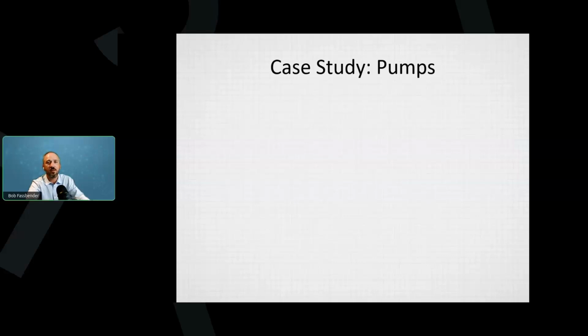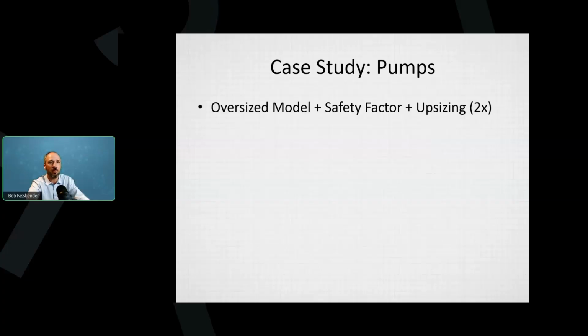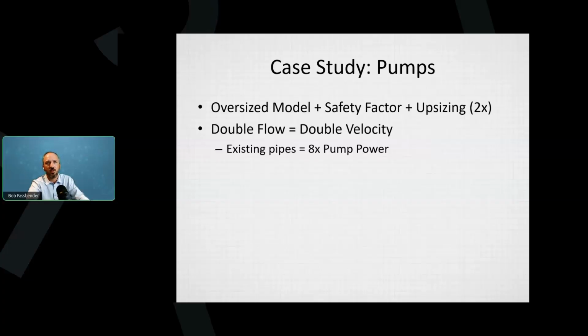In this case study, we'll look at pumps. Pumps and fans tend to be really significant players in this, and it's not entirely the model. It's this iterative process. Okay, so we have the oversized model, the safety factor, the upsizing. We're double. So double flow, and now we have double velocity. We do our pump laws. Say we have existing pipes, we end up with 8 times the pump power.